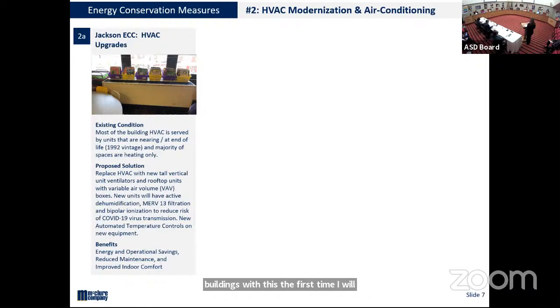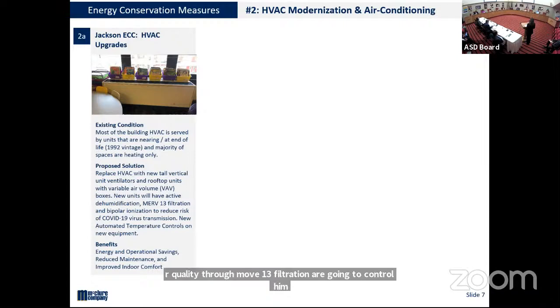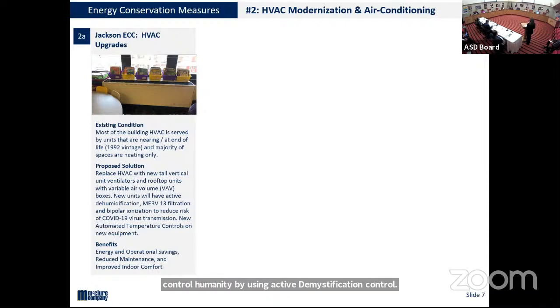The first building is Jackson. That HVAC equipment is from 1992. As a rule of thumb, HVAC equipment can last 20 to 25 years in a school, so it's beyond its useful life. It's heating only, so we're recommending replacing that equipment with tall vertical heat pumps and rooftop units. In addition, we're going to address indoor air quality through Merv 13 filtration, control humidity using active dehumidification control, and install bipolar ionization, which allows your filters to act more efficiently and take particles out of the air. These will all be strategies used to mitigate COVID-19, in addition to modernizing your HVAC systems and adding air conditioning.